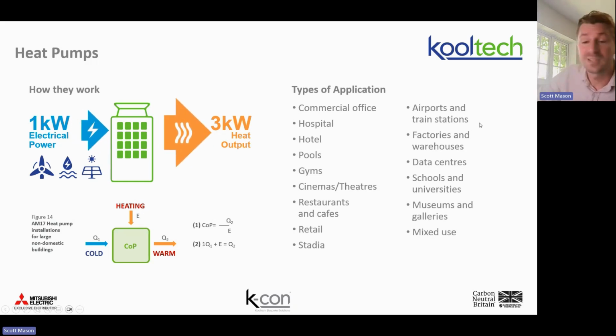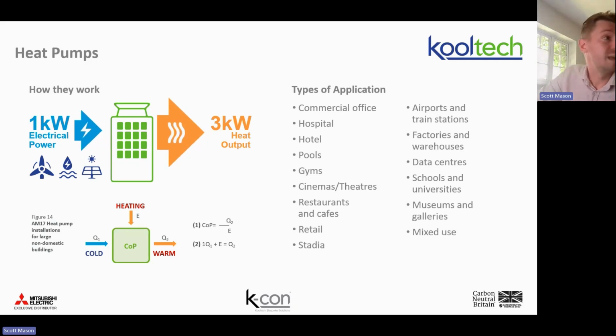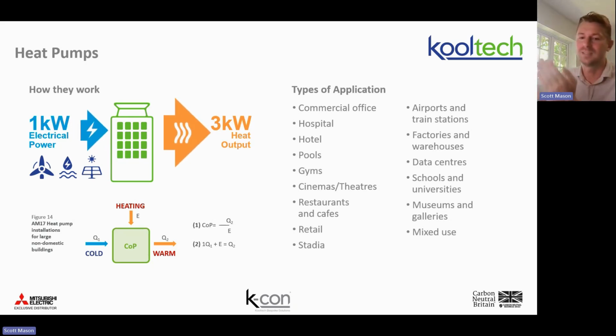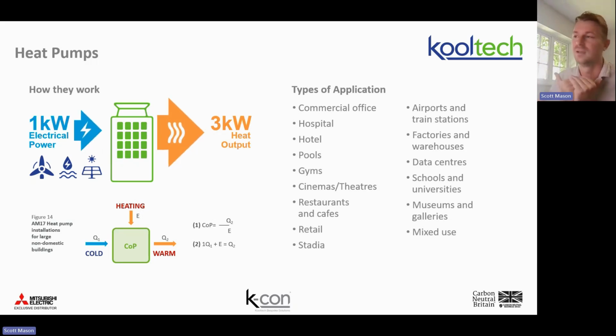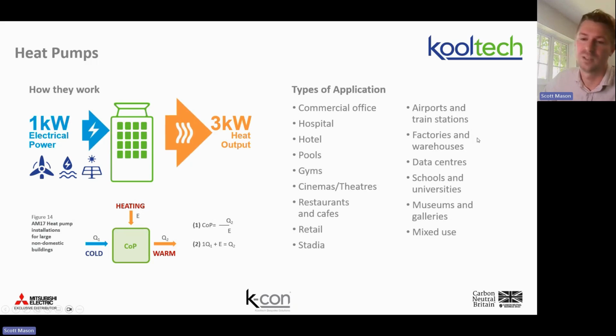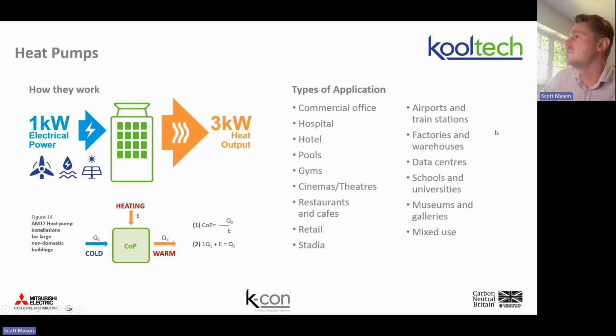The other barrier is going to be things like noise. So the CAHV doesn't really have much positive pressure coming off the fan outlet, something like 10 pascals. So as a result, it's really, really quiet. However, if I was in a hotel trying to sleep, would I want one outside my window? Maybe not. So again, there are different levels, and me saying something's quiet, well, quiet doesn't really mean anything, does it? A whisper can be quiet, but so can a shout if you're in an open field. So realistically, again, this is a job-by-job metric, and all of those decibel values can be published, and we've got availability for all of that. So as you're doing your analysis to work out whether the siting is appropriate, we would support that process with site-specific data. What are the other barriers going to be?